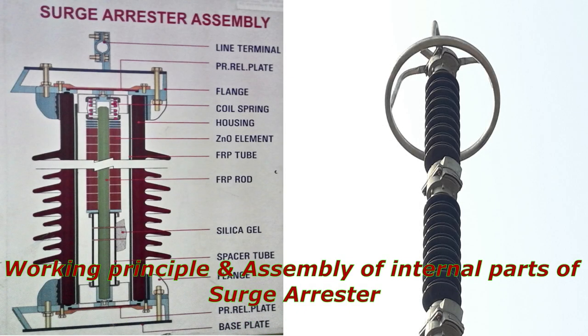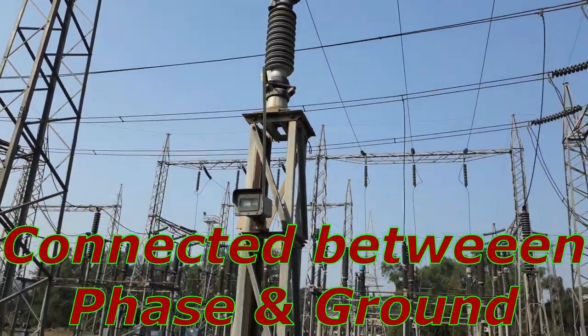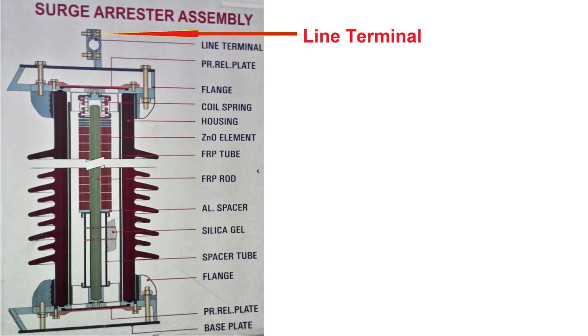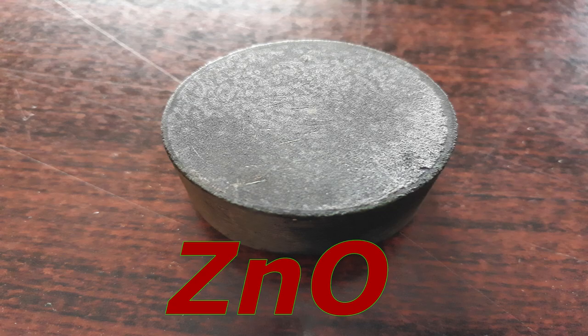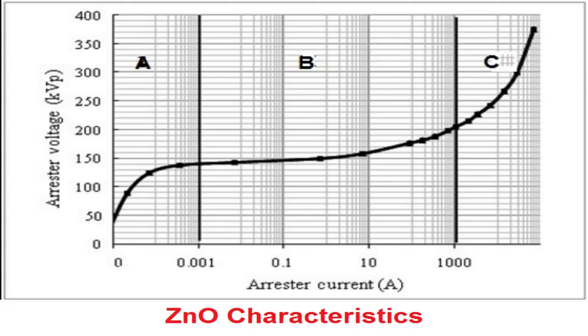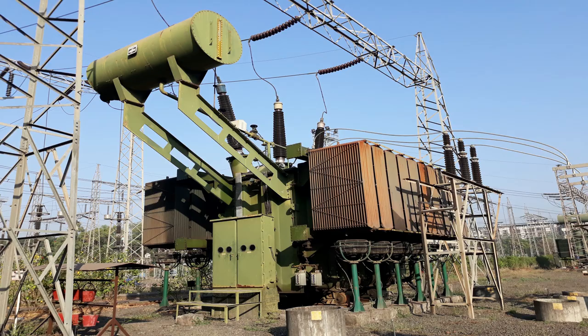Now let's see the working principle and assembly of internal parts of Surge Arrester. Surge Arresters are connected between phase and ground terminals. If we cut open a Surge Arrester, we can see the line terminal connected to the phase live terminal, and the bottom terminal connected to ground. We can see a column of ZNO pieces inside, which plays an important role in LA working. If we look at ZNO characteristics, it offers relatively high resistance at low voltage level and very low resistance at high voltage level. Hence whenever a high voltage surge occurs, the Surge Arrester offers the least resistance path and current flows through it to ground, avoiding any other path. Hence all other equipment such as transformers do not experience the high voltage surge.